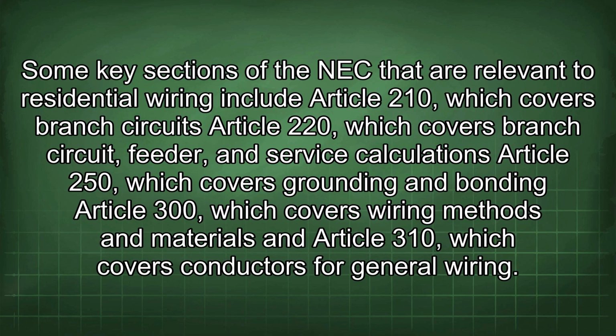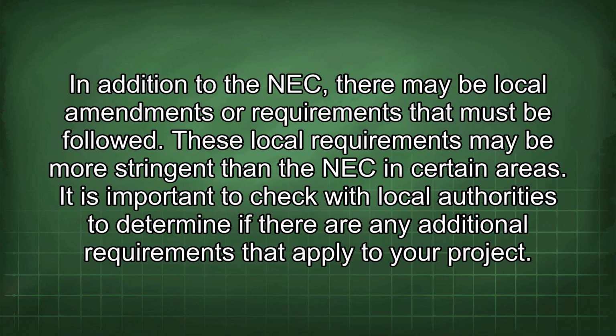Some key sections of the NEC that are relevant to residential wiring include Article 210, which covers branch circuits, Article 220, which covers branch circuit feeder and service calculations, Article 250, which covers grounding and bonding, Article 300, which covers wiring methods and materials, and Article 310, which covers conductors for general wiring. In addition to the NEC, there may be local amendments or requirements that must be followed. These local requirements may be more stringent than the NEC in certain areas. It is important to check with local authorities to determine if there are any additional requirements that apply to your project.